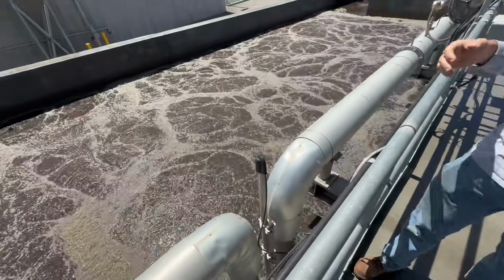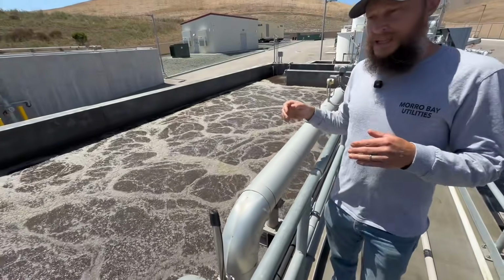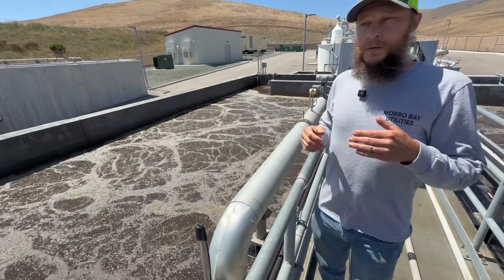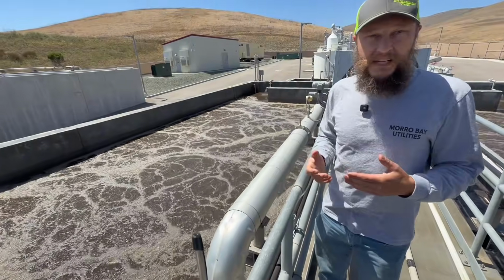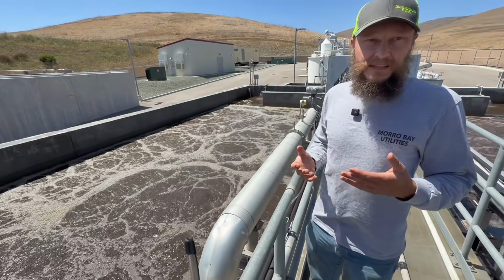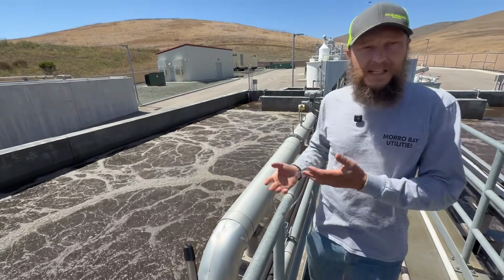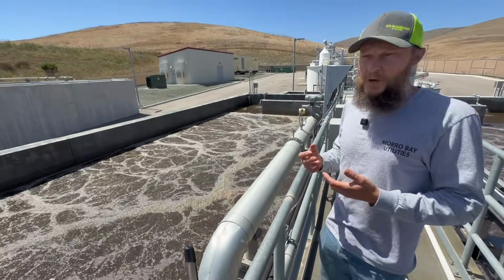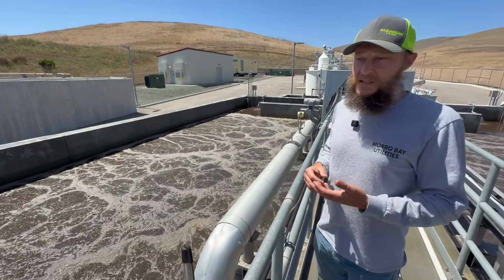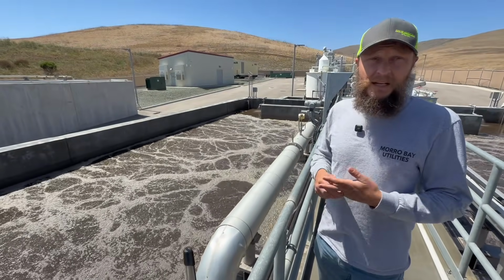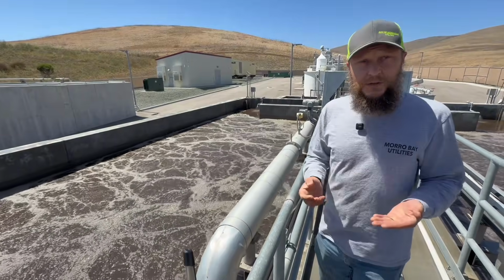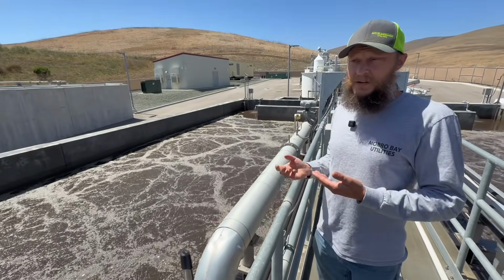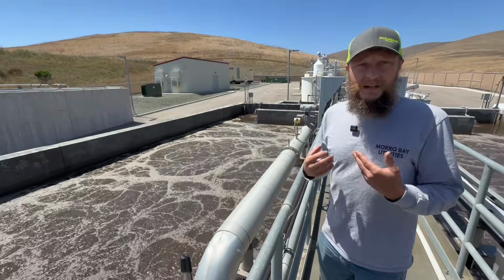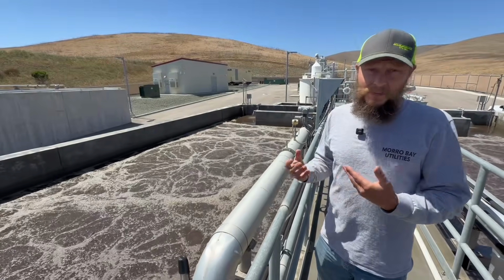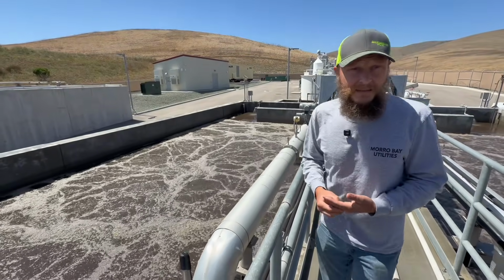One of the things that's super important is that you get reliable numbers in your SCADA system, and you can't just rely on SCADA itself. There's tons of sensor maintenance that needs to happen. Probes need to be cleaned and sometimes calibrated at regular intervals to stay true. And so the numbers that we get on SCADA are only as good as our sensor and probe maintenance.